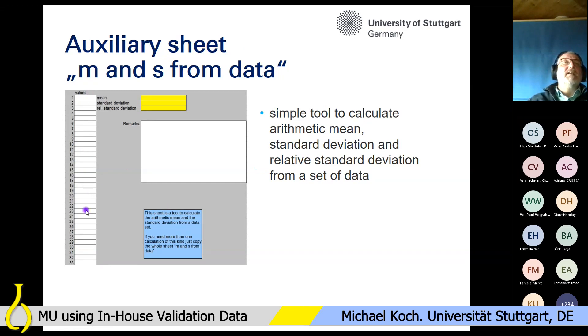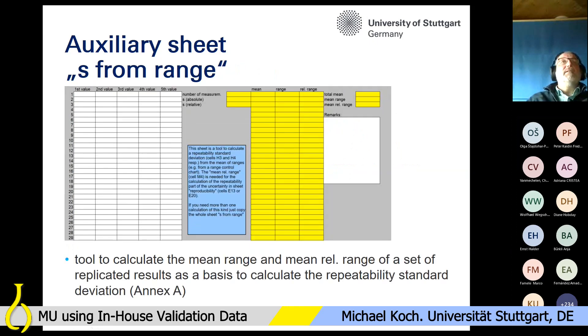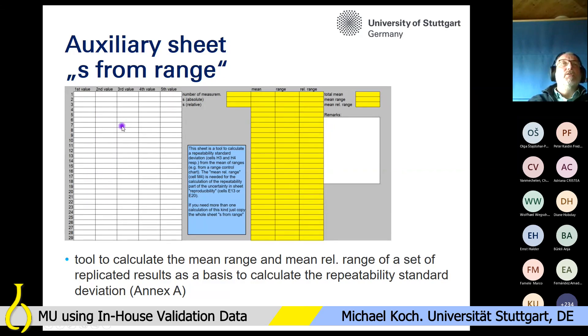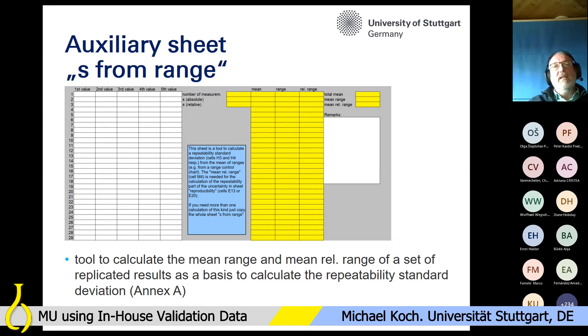The file comes with some auxiliary sheets. One very easy sheet lets you enter data and get the mean, standard deviation, and relative standard deviation. There is also a sheet for calculating a mean range or mean relative range from multiple determinations. This has been changed in the newer version of the Nordtest technical report, which uses pooled standard deviation from calculated standard deviations. The old version of the Nordtest report calculated standard deviation from a mean range using a simple factor.